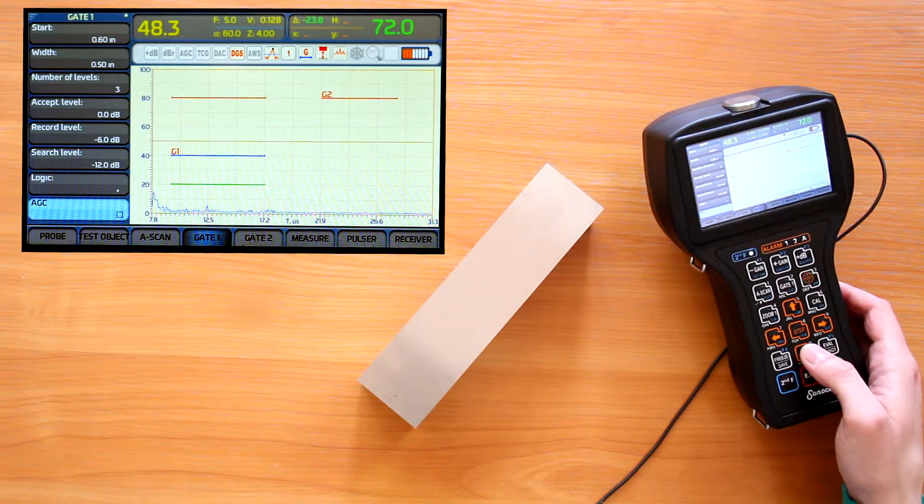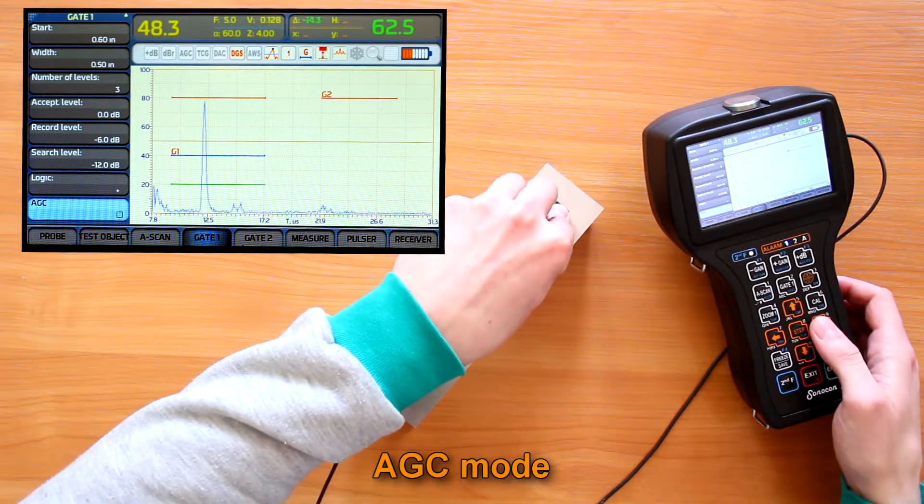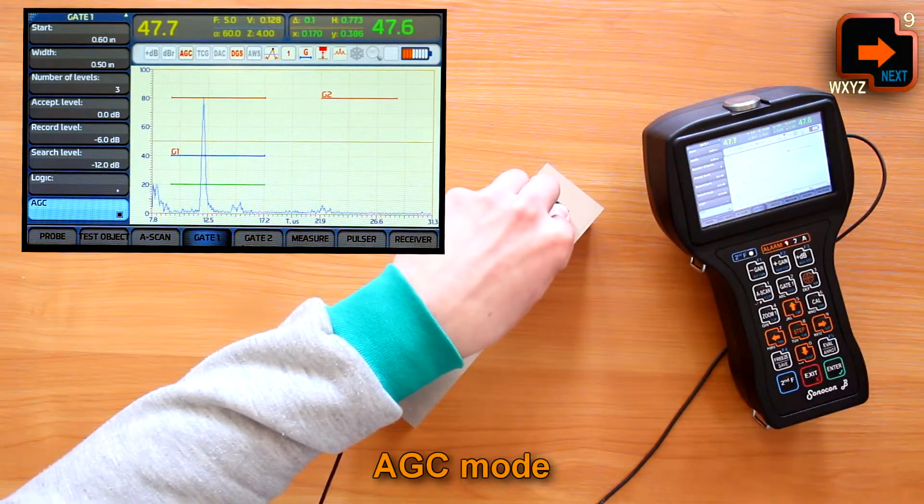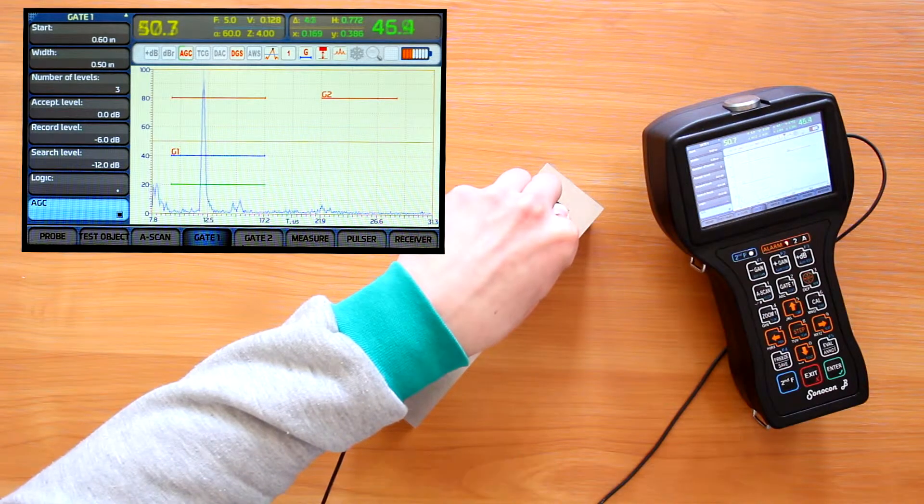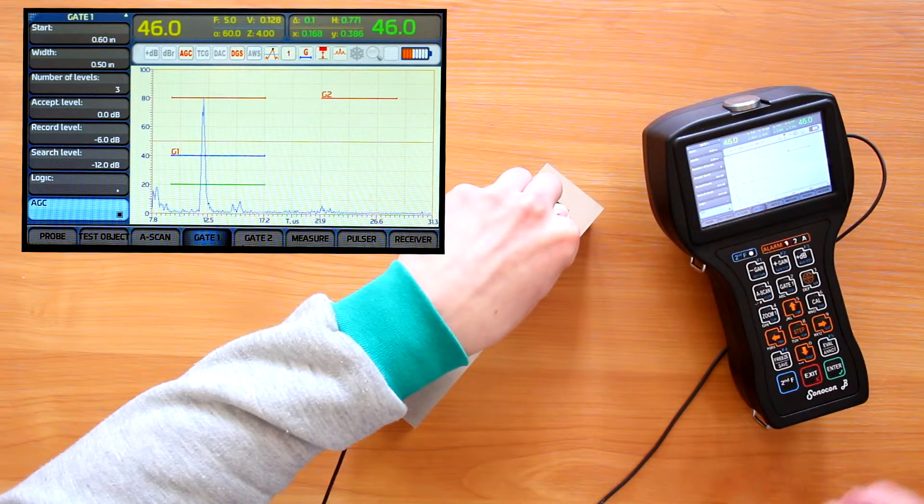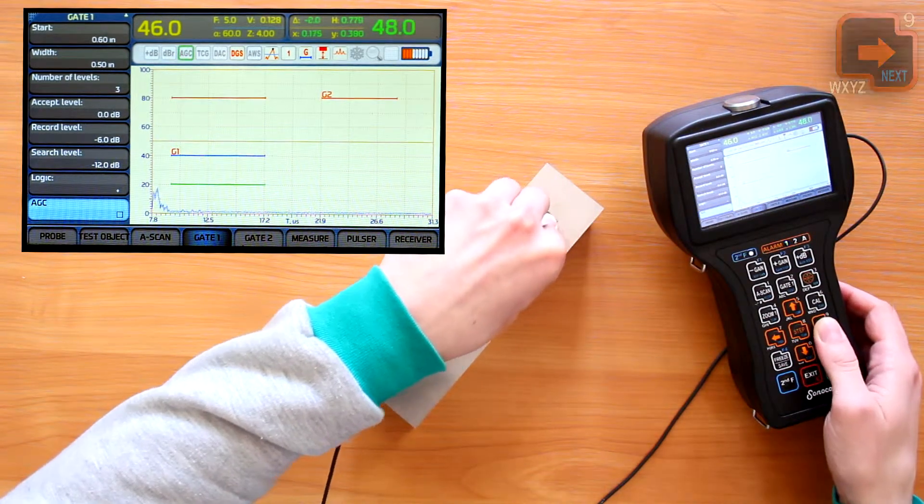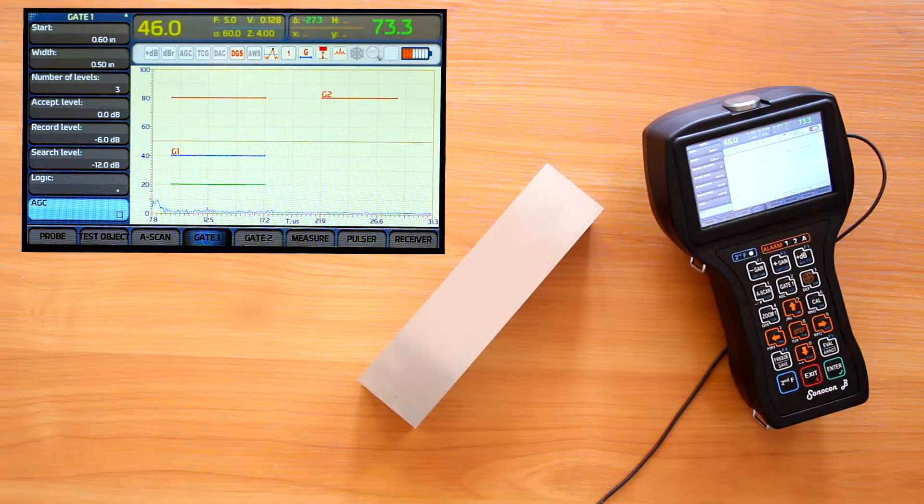And finally, we can toggle AGC mode for each gate. Which is helpful for example for reference signal gating. Which allows to automatically compensate sensitivity change due to coupling conditions.